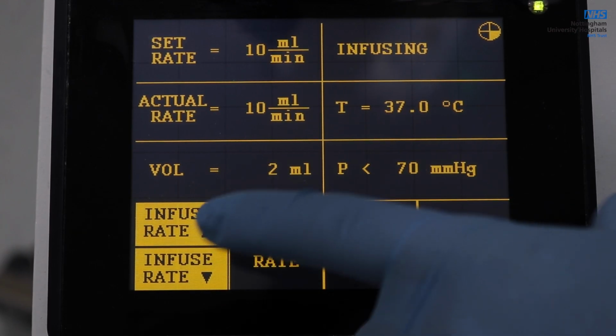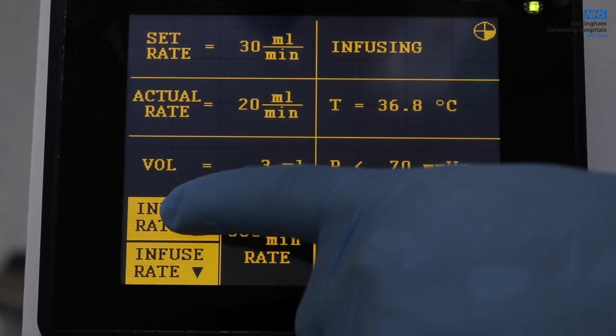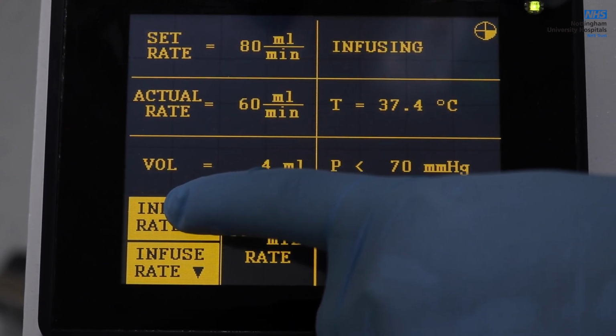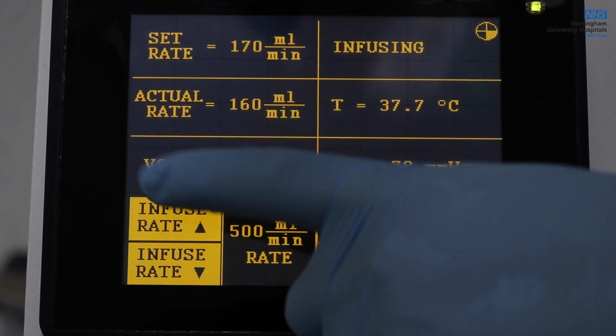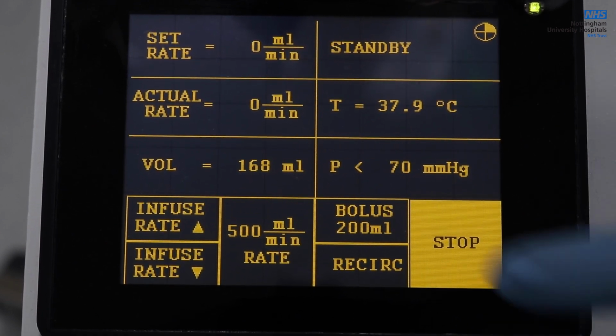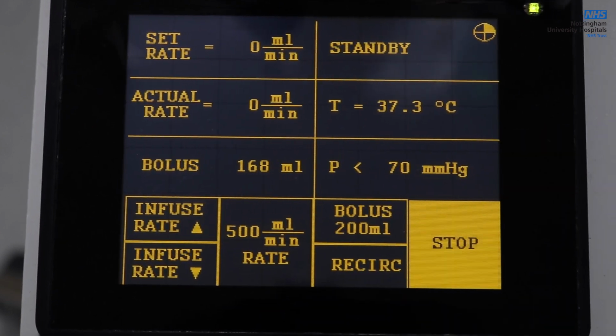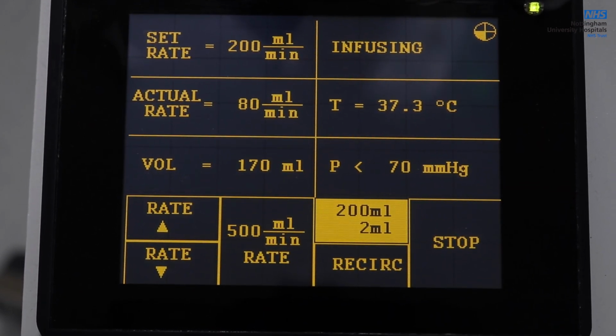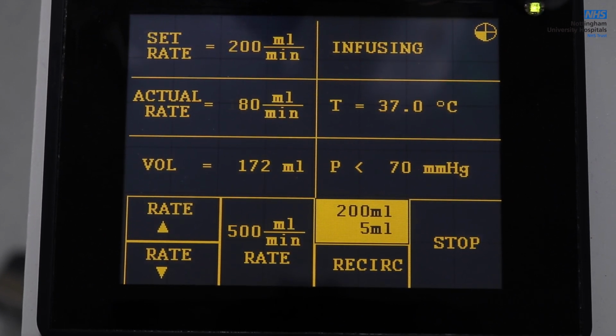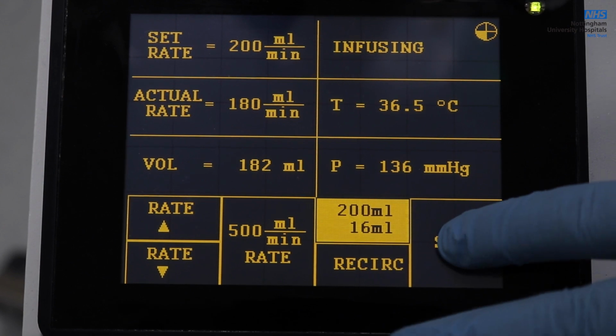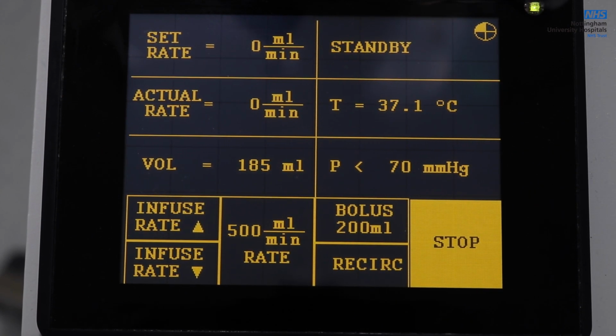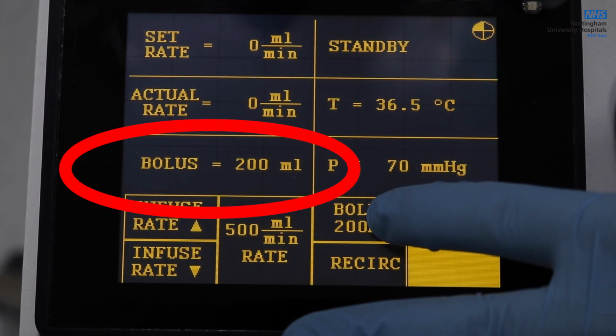How to change the infusion rate. Press and hold either the up and down infusion rate button on the display until the desired rate is reached. To infuse a fixed bolus volume, a single press of the bolus button will deliver the preset bolus to the patient. To change the bolus amount, the device must stop infusing. Then the bolus button can be held until the desired bolus amount is displayed.